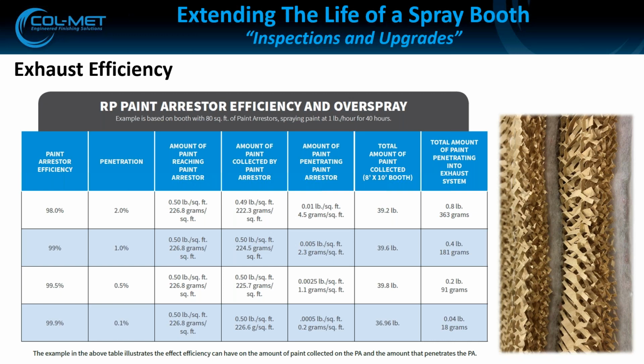If you're spraying a clear coat, right, and let's just go crazy with it, and let's say you're spraying a clear coat with a Bell atomizer, well, the efficiency of that filter is probably below 50, maybe around 40 at that point, because our particulate curve is so low. We're able to shear that clear coat because there's no color pigmentation. We're able to shear it easily, make it smaller, micron sizes of particulate. So it's harder to catch. When you're spraying something out of a conventional spray gun that's a very high viscosity bake-on enamel, we're throwing a lot of rocks and marbles at it, I like to say, and we can catch that. So it's important to understand where that efficiency plays into this.